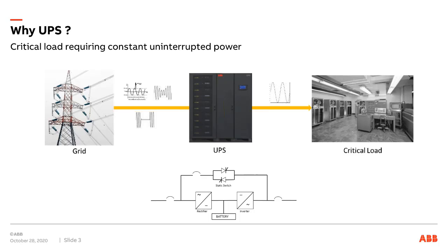The level above the rectifier and inverter is the third power module in a UPS, the static bypass switch. That's a save the day device. If something happens downstream where the inverter cannot feed that load, it can be an overload or a short circuit, or could also be a fault in the inverter. Regardless, the UPS control will detect that there's a load situation that the inverter cannot handle, and it'll fire the static switch, it'll transfer the load directly to utility power. So if it's an overload, it'll clear, hopefully trip the breaker or blow a fuse, and the UPS will go back to the inverter. That's the basic functionality of the UPS.